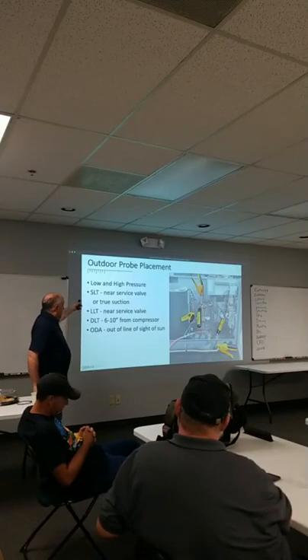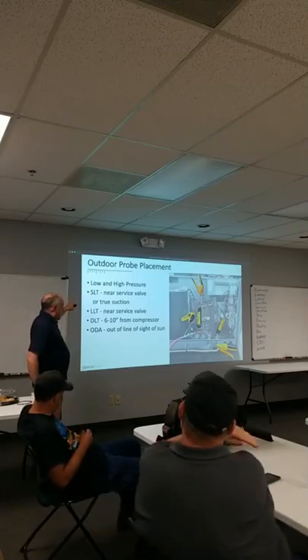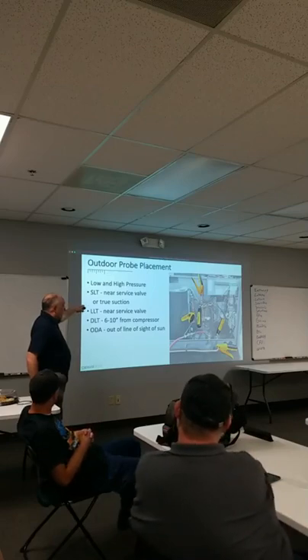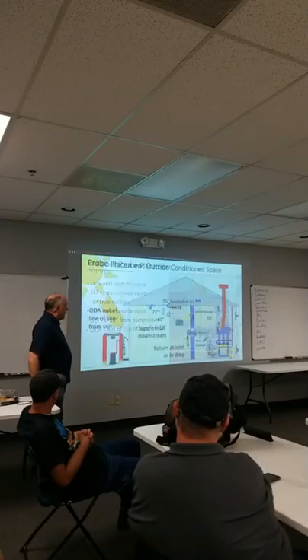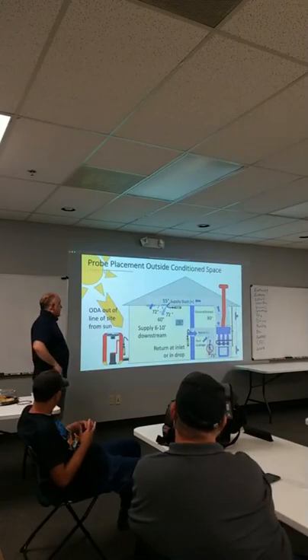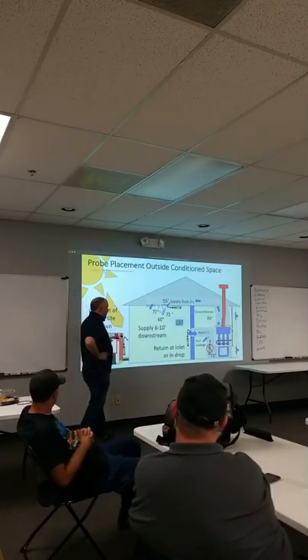So we wanna make sure that we're on the correct ports. We wanna be on the true suction line, if we're talking a heat pump, right? Liquid line near the service valve, discharge line 6 to 10 inches away from the compressor, outdoor air out of line of sight of the sun, right? This is another interesting problem we get right here, it's called entrainment.